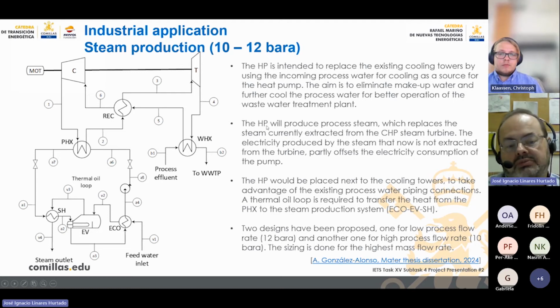Okay, the heat pump will produce process steam here, which replaces the steam currently extracted from the CHP steam turbine. The electricity produced by this steam that now is not extracted from the turbine partially offsets the electricity consumption here of the pump. The heat pump will be placed next to the cooling tower to take advantage of the current pipes, and this meant that we have used a thermal oil loop in order to move the heat produced here to the production of the steam here near the factory.